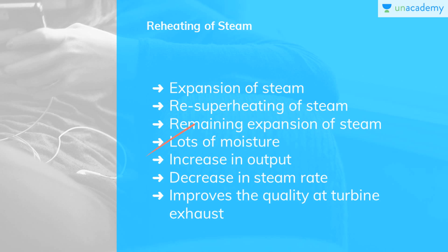Had the higher pressure been used without reheat, the cycle would have been 1 to 4s to 5 to 6s, with a lot of moisture at the turbine exhaust having quality x4s, that is the dryness fraction. With the use of reheat, area is added to the basic cycle. The net work output of the plant increases with reheat because H3 minus H4s is greater than H2s to H4s. Whether the cycle efficiency improves with reheat depends on whether the mean temperature of heat addition in process 2s to 3 is higher than that in process 6 to 1. By increasing the number of reheats, still higher steam pressures can be used, but the mechanical stresses increase in a much higher proportion than the pressure because of the prevailing higher temperature.